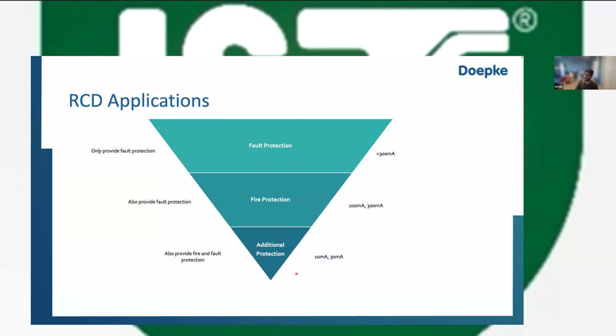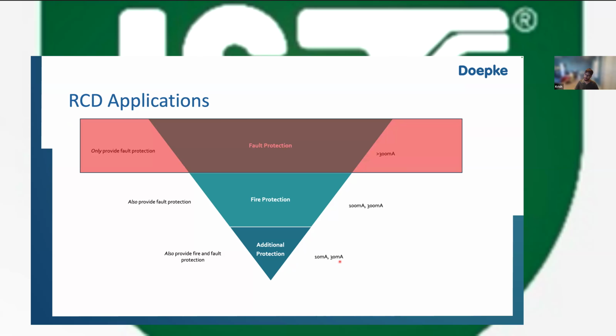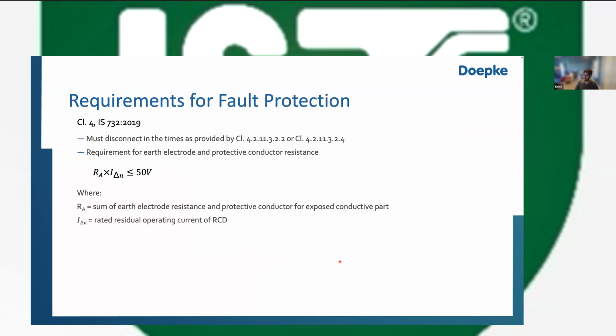We now pivot slightly to what the RCD is and how it works. So an RCD is a residual current device, as we know, and as I explained. There are 2 types that we want to talk about in this webinar, which is the RCCB and the RCBO. But in general, we'll use the term RCD because they apply to all those devices. There are 3 reasons why you use an RCD in any electrical installation. Today, I want to focus specifically on fault protection.